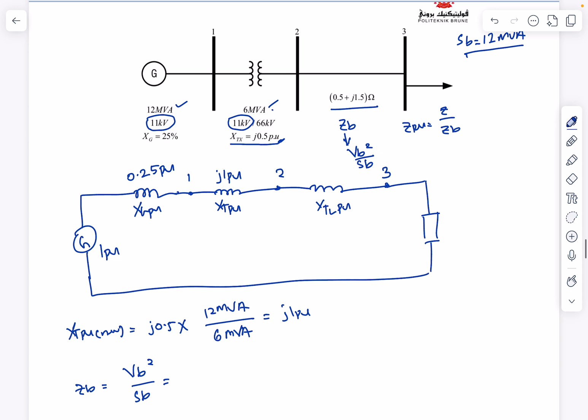For the transmission line, first you need to calculate the base impedance ZB. Once you get ZB, ZPU equals Z divided by ZB. ZB equals VB squared divided by SB, where the voltage here is 66 kV. So ZB equals 66 kV squared divided by 12 MVA, which gives an impedance base of 363 ohms.